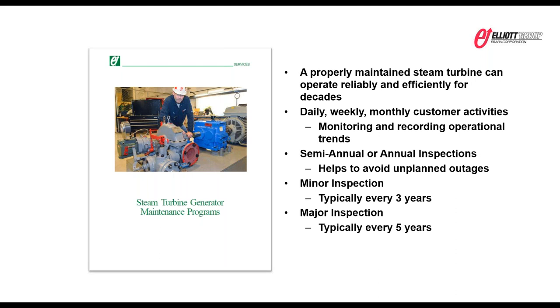Now, major inspections every 5 years, let's say that's your 100,000-mile inspection. That's where you're really breaking everything down. These are during scheduled shutdowns. We're going to open up the top half of the casing, inspect the internals, look at the rotor, the nozzle rings and diaphragms, things like that, and replace any parts that are needed. Of course, we're going to go through all of that with the turbine, the gear if there is one, the generator, the oil system, everything that's in our realm, in our scope, would be gone through with a fine tooth comb.